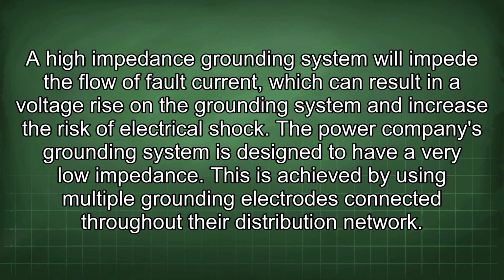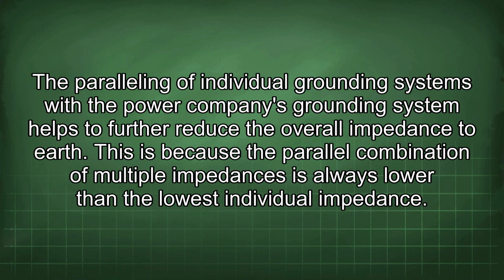The power company's grounding system is designed to have a very low impedance. This is achieved by using multiple grounding electrodes connected throughout their distribution network. The paralleling of individual grounding systems with the power company's grounding system helps to further reduce the overall impedance to earth. This is because the parallel combination of multiple impedances is always lower than the lowest individual impedance.